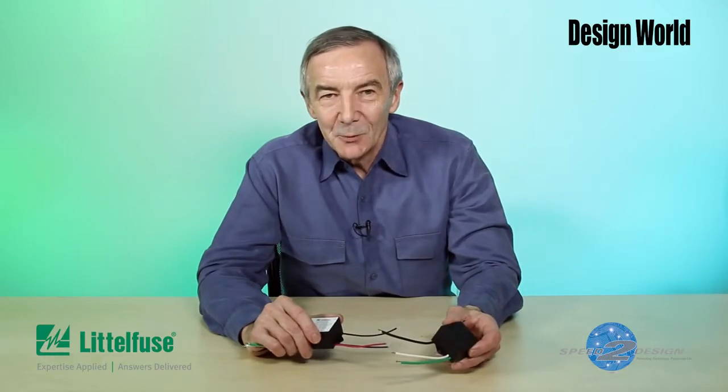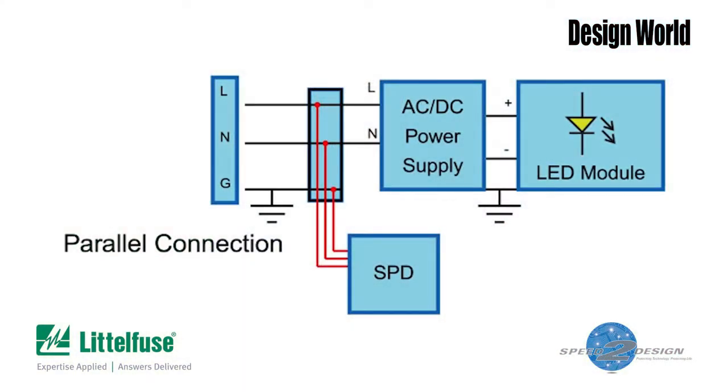There's a UL standard for surge protective devices on AC lines, and to comply with it you have to design in some kind of protection to prevent the MOV from failing this way. That protection has traditionally been a thermal fuse or thermal cutoff device in series with the MOV. And that's basically what Littelfuse did with its varistor modules. You can get these modules for parallel or series connections, and the connection scheme for each case is slightly different.